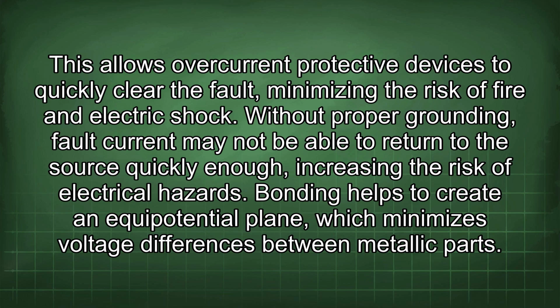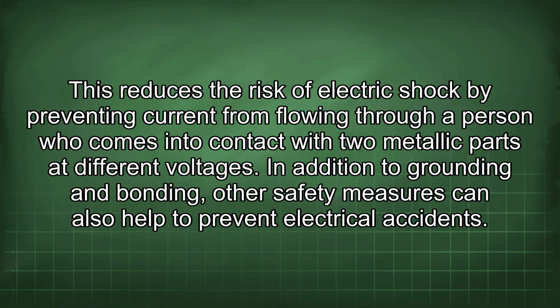Without proper grounding, fault current may not be able to return to the source quickly enough, increasing the risk of electrical hazards. Bonding helps to create an equipotential plane, which minimizes voltage differences between metallic parts. This reduces the risk of electric shock by preventing current from flowing through a person who comes into contact with two metallic parts at different voltages.